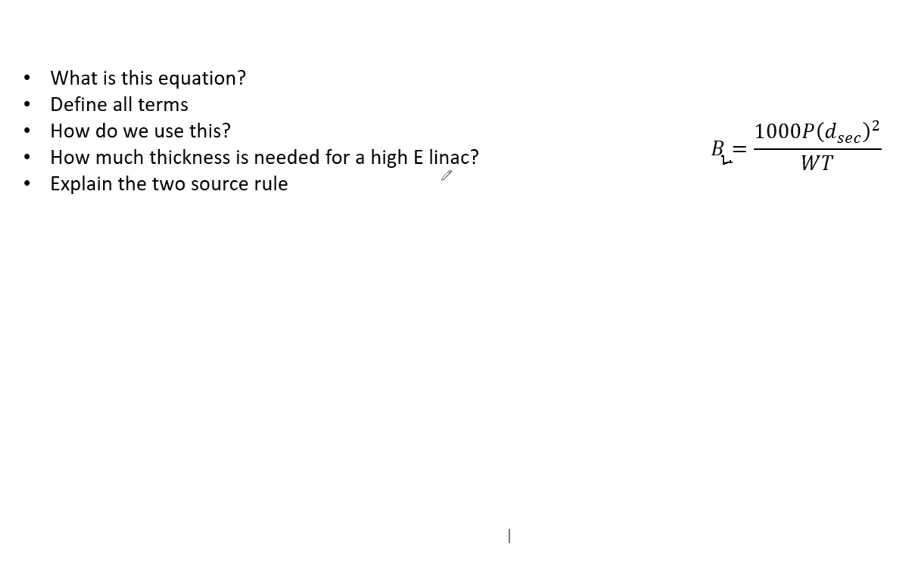And so now let's define all the terms. So we have 1000. Thankfully, this clues us in immediately that we know this is leakage. And the reason we know 1000 really helps us is because linear accelerators are required to attenuate the head leakage to 0.1% of the primary beam. So that's why we have 1000 in here. If you see 1000, you know immediately that is leakage.